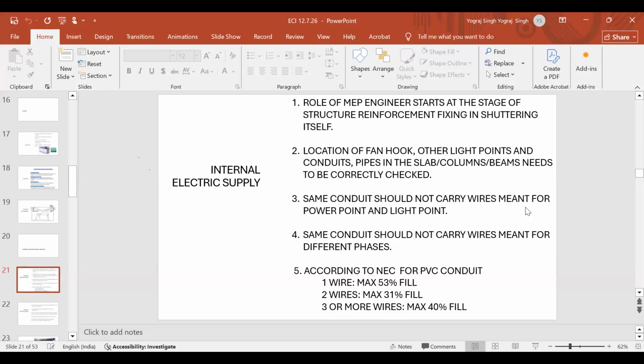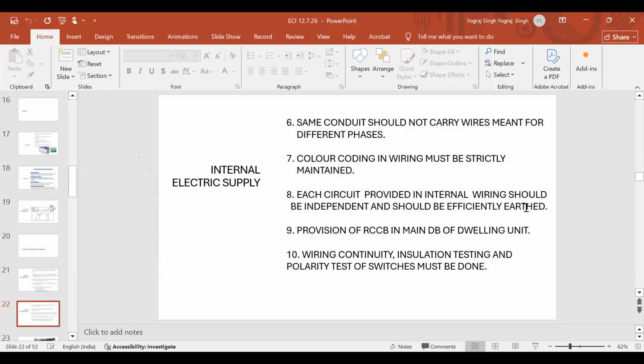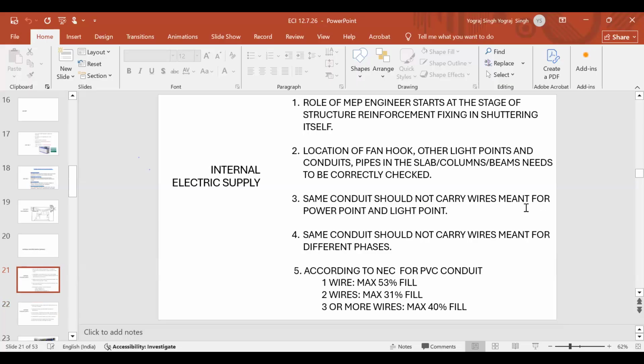There are props all over. Partition walls are not there, so you do not know. But the drawing shows the location of fan and light points correctly. Whether that location is correct or not matters, because later partition walls will come. I have seen a fan hook provided just about 40 centimeter away from the wall. That was the good old time when drawings were made by hand, by pencil. The person doing this is not a learned one, not a literate one. Marking of fans and light points can have errors. That has to be seen by the MEP engineer during the slab casting stage.